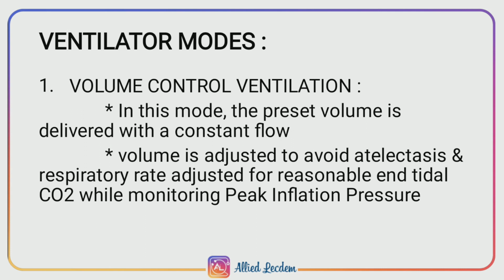Volume control ventilation can be delivered by several modes, including controlled mechanical ventilation (CMV), assist control (AC), and synchronized intermittent mandatory ventilation (SIMV). With volume controlled modes, the clinician must set the desirable tidal volume, respiratory rate, and positive end expiratory pressure, also known as PEEP.